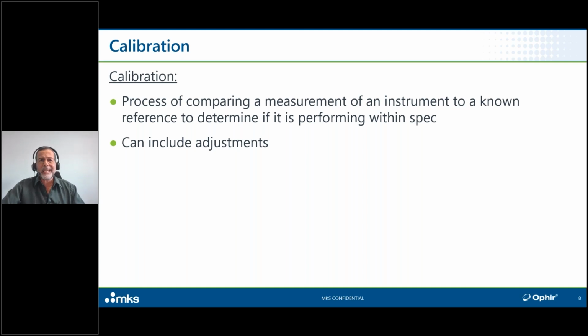If I give you a measurement instrument and I tell you that this instrument reads to within plus or minus 3% of NIST, then that's fine. Even if I tell you that it reads 10% below NIST, to within plus or minus 3%, that's also fine, because then you know that you add 10% to what you read, and then you have a reading that's within plus or minus 3% of NIST. So even if I didn't actually make that adjustment, if I tell you exactly what the deviation is between this instrument and NIST, that's good enough. In practice, a commercial supplier of measurement equipment like Ophir will generally, yes, do that adjustment step.